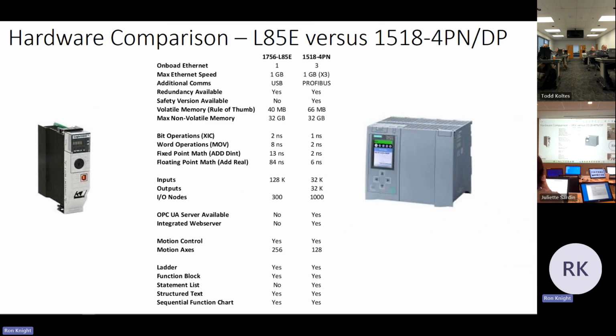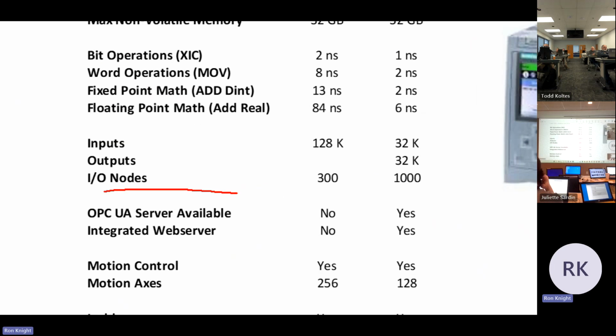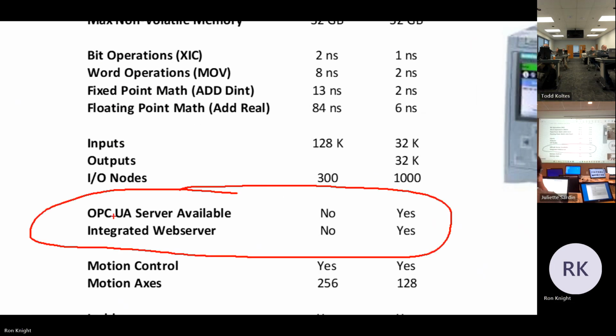It really depends. One of the big differentiators for me is the bells and whistles. This is just a couple of them, but there is an integrated OPC UA server inside both the 1500 and the 1200 PLC. Hopefully you're familiar with OPC, but imagine you've got a third-party HMI application, and it needs to talk to your Siemens PLC. In the old days, you'd go through some type of OPC server like a Kepware or a Matrikon. You don't need to do that. The PLC itself can be an OPC UA server and serve that data up to anybody's OPC UA client. Now, it's licensed separately, but it is a lot less expensive than a Kepware or a Matrikon.